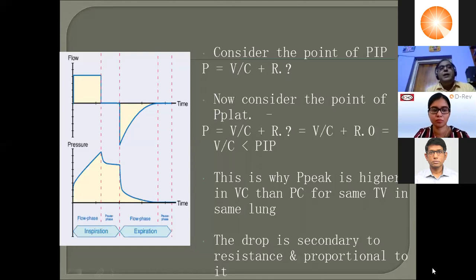If it is on VC, you will see you are needing a peak pressure of say 24. But you change over right then at that point to PC and go up on your PIP till you reach your tidal volume of 500. You will see that it is not 24. It will be somewhat less than that, maybe 21 or 22. That is because of why.